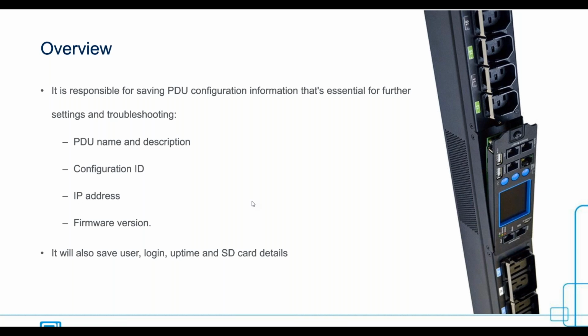It will manage configuration information. This is essential for specific settings that may be required or even for any troubleshooting that needs to be performed. The MCM also holds information about the PDU name and its description, the configuration ID assigned to the PDU, its IP address, the firmware version, and any other settings related to the functionalities of the PDU. It's important to note that any user login, uptime, and SD card details will be saved in it as well.